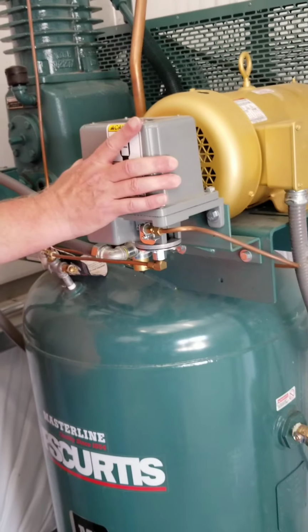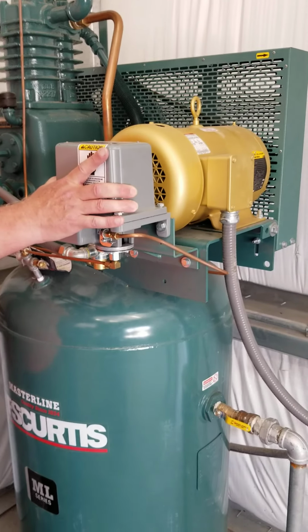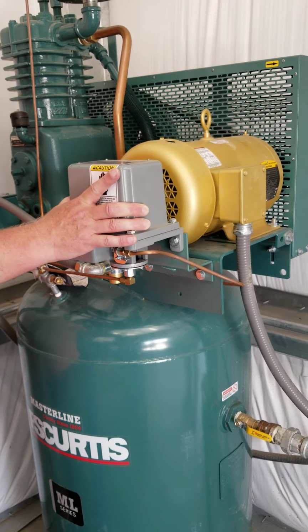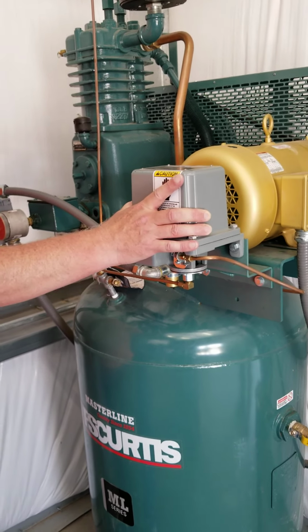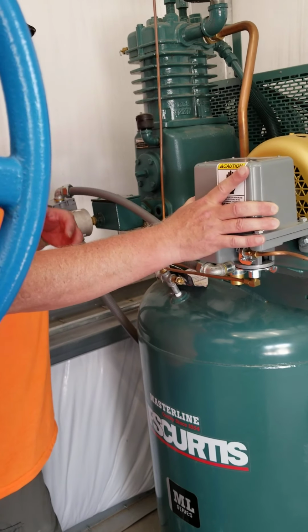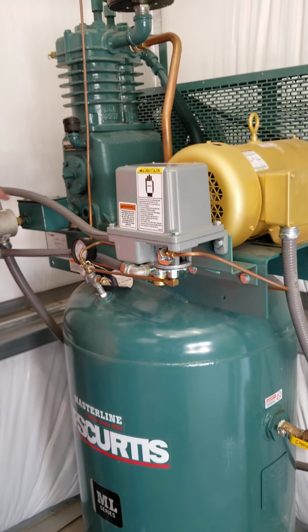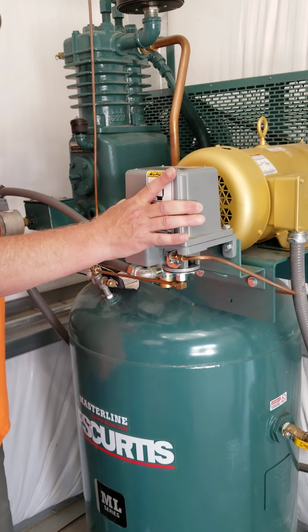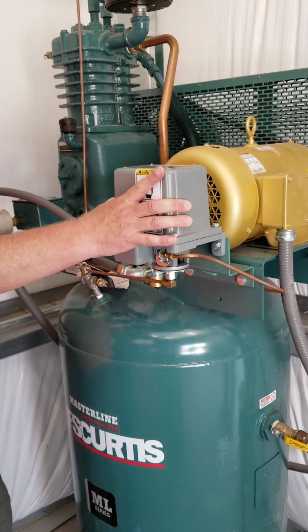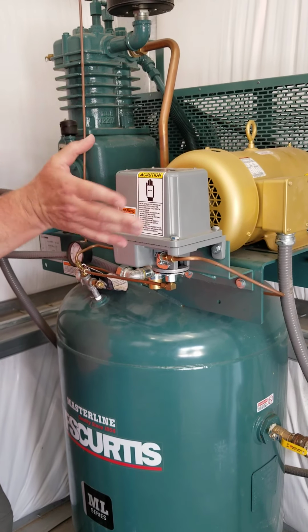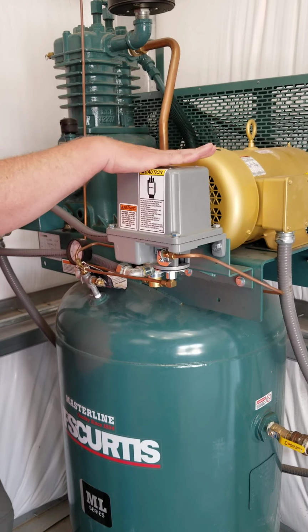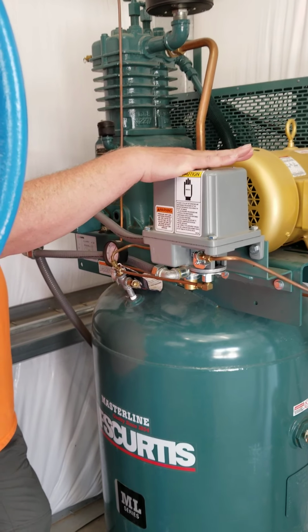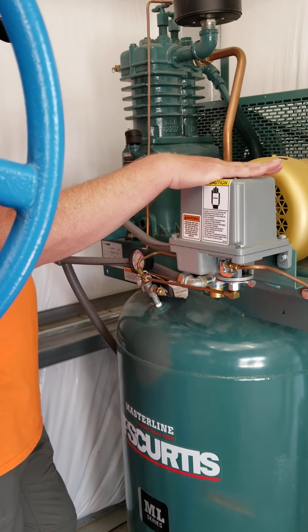You have a pressure switch. This is what turns them on and off. It's a standard pressure switch. Clockwise increases pressure, counterclockwise decreases pressure. They're currently set to turn on at around 170 and off at 190. And that's based on your system pressures you're going to be running. This always needs to be at a higher pressure to be able to push air out to your surge tank.